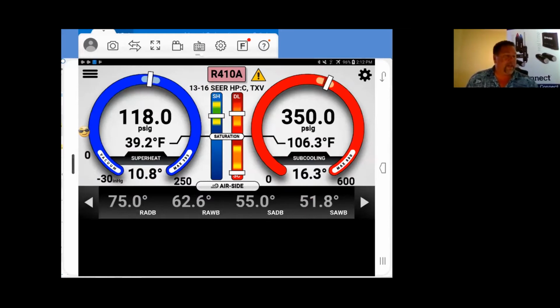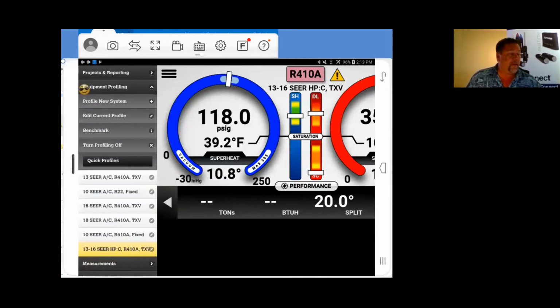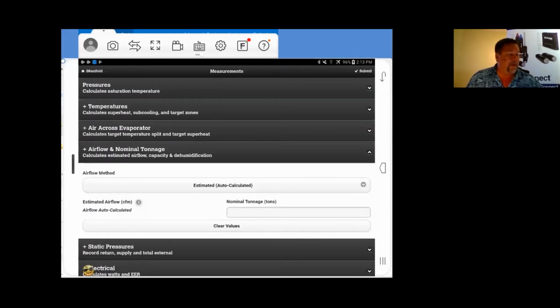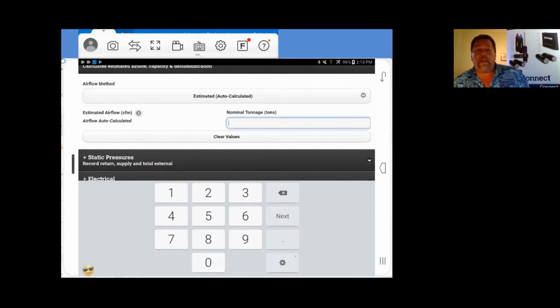But now taking a look at this, our profile's set. All of our calculations are there for that. We still do not have any airflow because we didn't put in a tonnage. Tonnage of the system is very simple. You take a look, what are we working with? This is a 3, 4, 5 ton unit. We go up in here to our 3-bar menu again, open it up, go down to measurements. Tap measurements, airflow and nominal tonnage. There's our nominal tonnage. This particular system is a 5-ton unit. So right here in nominal tonnage, we tap in 5.